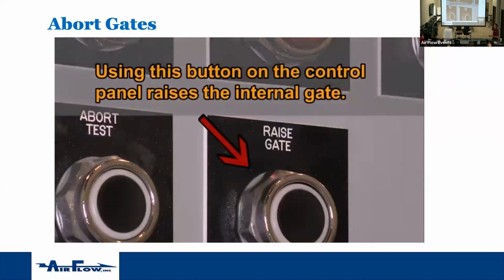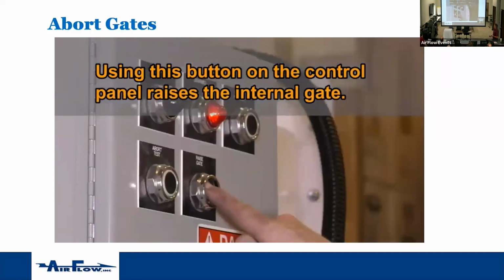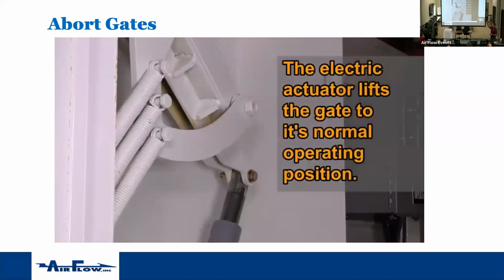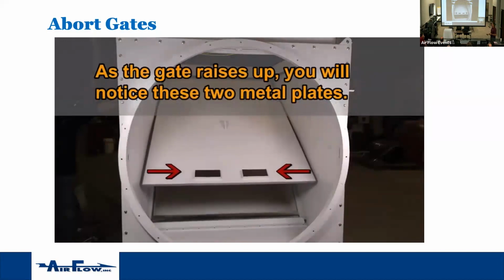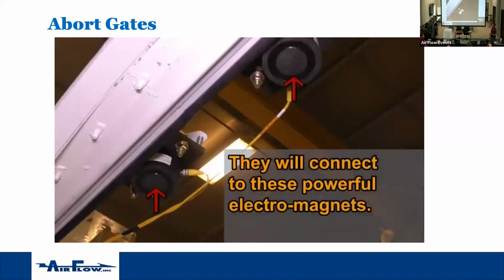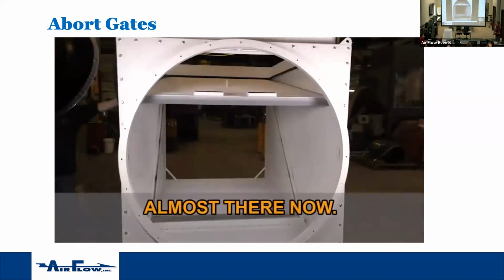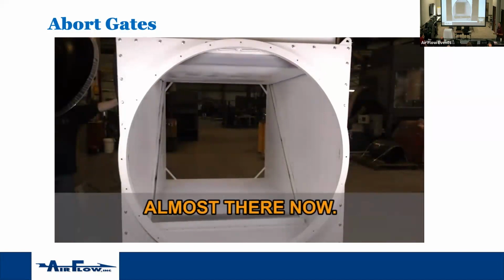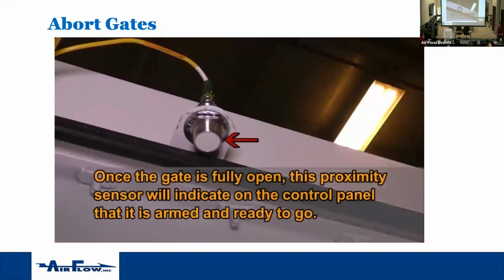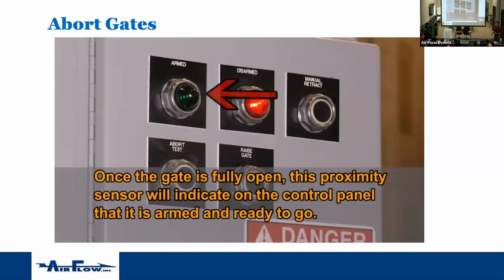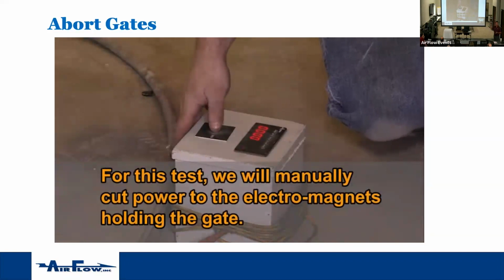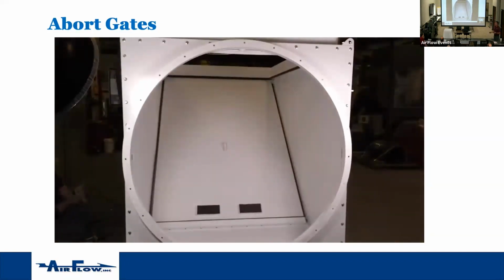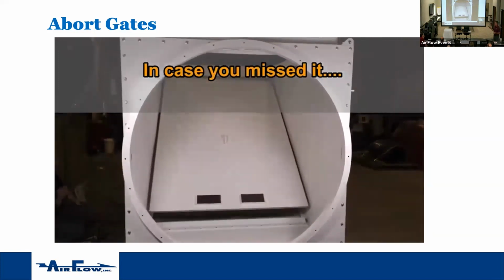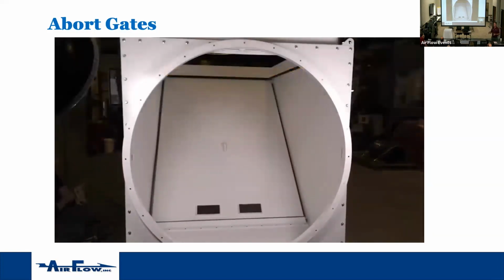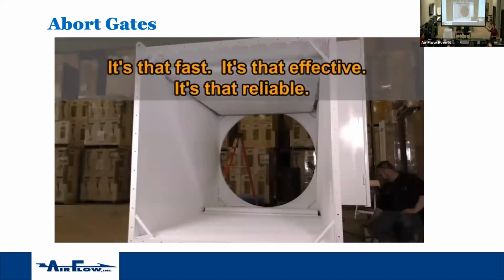Control panel will be mounted on the side of the abort gate. To arm it, you'll hit the raise gate button and hold it. And a cylinder will set that abort gate up and hit the magnets. So these are just two plates. The magnets will sit up here. When it's up, there'll be a proximity switch mounted on the side of it. It'll tell the system, I'm in the arm position, I'm up. Then that red light will switch to green and you'll be good. And then when the spark is seen, it actually cuts power to the magnets. So it'll cut power to the magnets, some catastrophic thing happens, the magnets will lose power and the plate will drop.